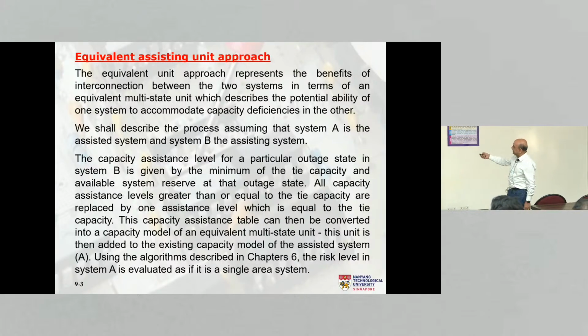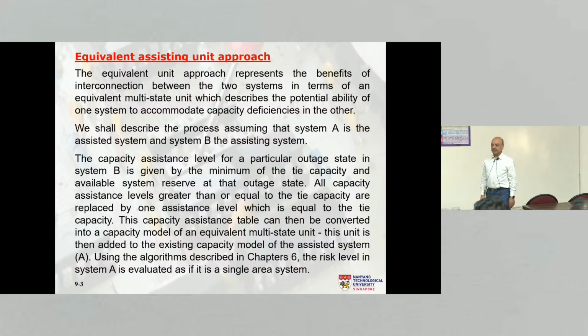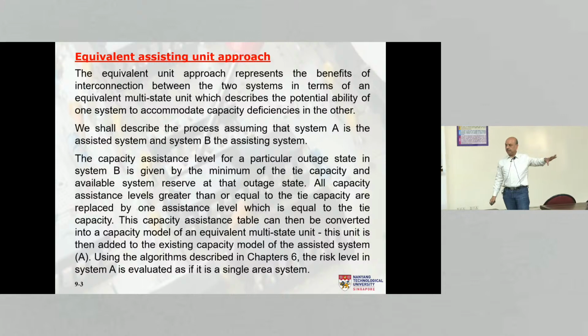So the capacity assistance table from system B can then be converted into a capacity model of an equivalent multi-state unit. In general it will be multi-state, maybe two-state for simplicity. And then we add this unit to our existing capacity model in system A. So as a principle, this is the process. We'll go to system B, see how much support it's going to provide, see how much it can transport through the transmission line or cable, and then add that model to our own capacity model, recreate the new capacity model, and then use the load model and calculate the new risk. So that's the process in simplicity.